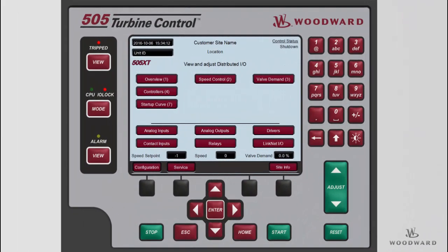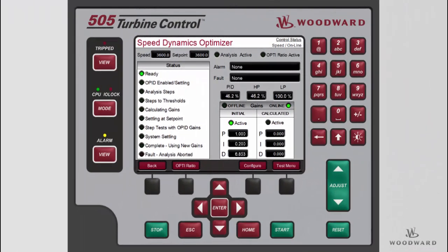We will now cover how to configure and run the optimizer test from the panel of the 505XT. The test can be accessed from the Speed Dynamics Optimizer page. From the home screen, navigate to the Speed Control page and press Enter. On the Speed Control page, use the Softkey menu to go to the Dynamics page. From the Dynamics page, press the PID Optimizer Softkey to see the Speed Dynamics Optimizer page.